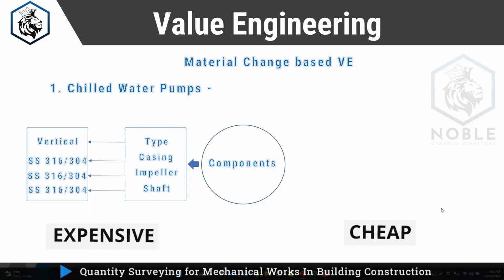Our specification asks for vertical chilled water pumps, SS316 or 304. SS means stainless steel, 316 is a grade and 304 is also a grade. So that means a high grade stainless steel is used for the casing, impellers and shafts.